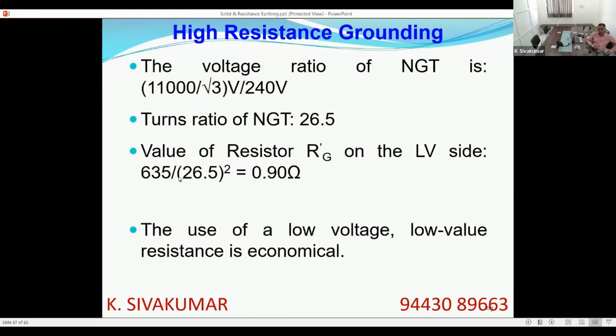Now here, for the same 10 ampere, we had to connect a 635 ohm, 6.35 kV rated resistor in case of directly connecting a resistor in the neutral to ground path. Here, if you provide an NGT, the NGT ratio is 11 kV by root 3 by 240 volt. The turns ratio of the NGT is 26.5. You connect only a 0.9 ohm resistor on the 240 volt side of the NGT. It will be reflected as 635 ohms on the HT side of the NGT, the 6.35 kV side. You will get the same 10 ampere current limitation on the HT side. So you see the biggest advantage: a low voltage, low value resistance becomes very economical and easy to handle also.